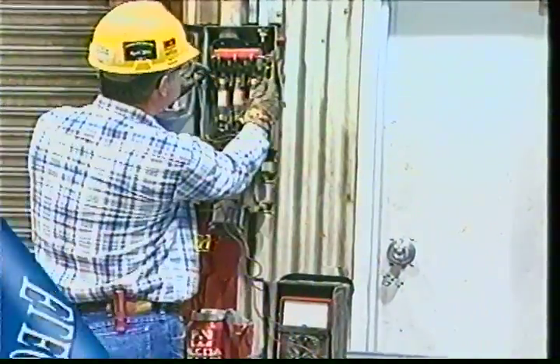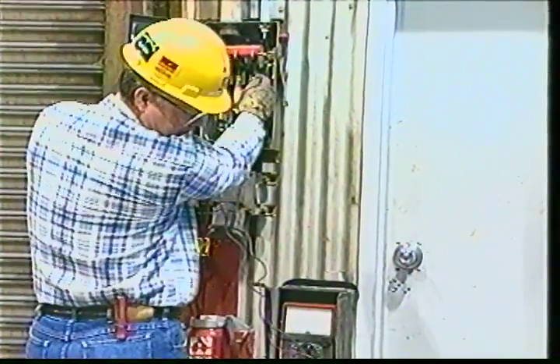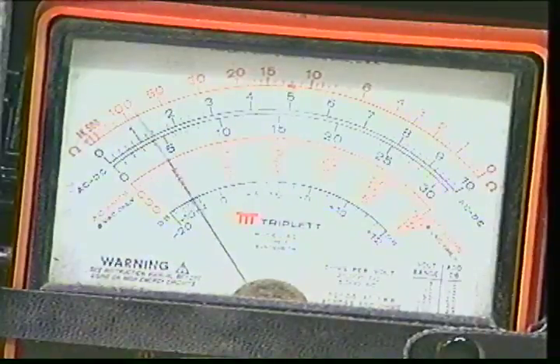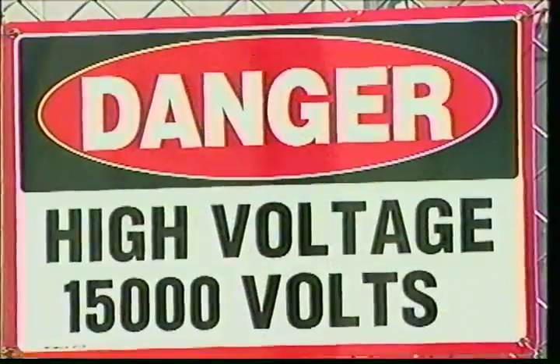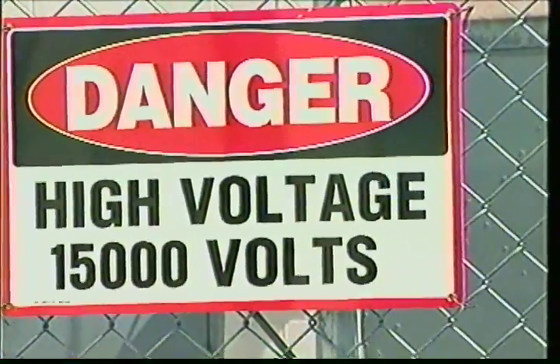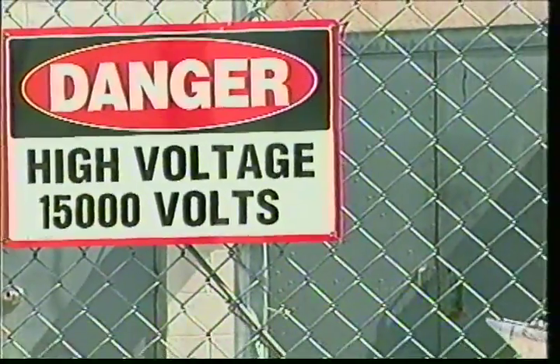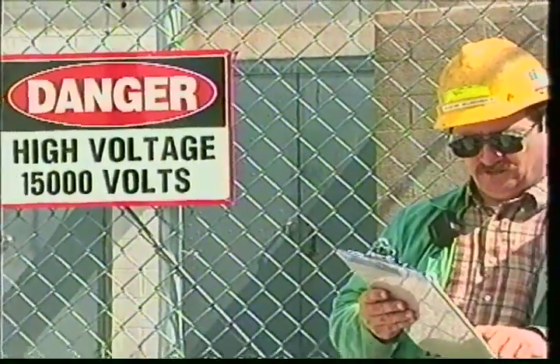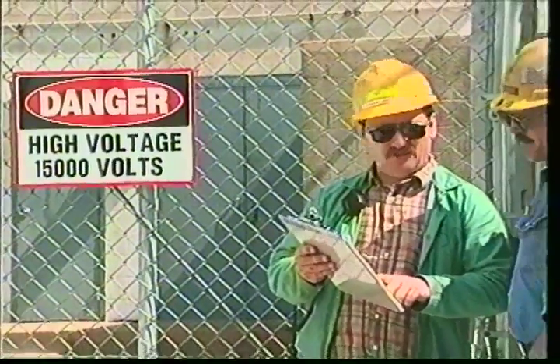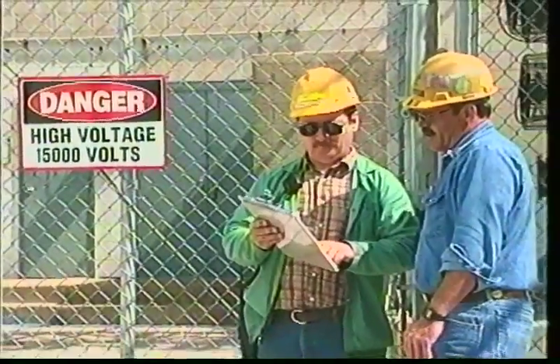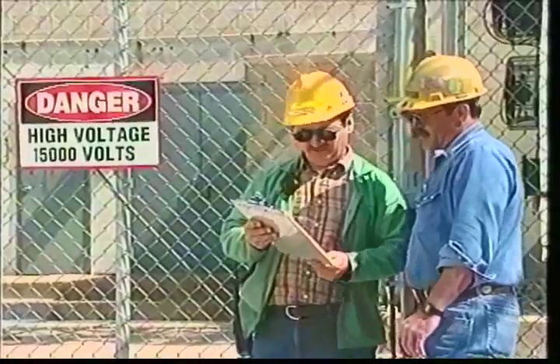When working around electricity, always assume the equipment is energized unless proven otherwise. Obtain a clearance if you are working in high voltage substation areas over 750 volts AC phase to phase and fenced substation areas on electrical distribution towers and similar structures. If any work is to be done in close proximity to electrical equipment, such as cable, bus, transformers, insulators, etc., which have open electrified connections, a job safety review will be held prior to starting work.